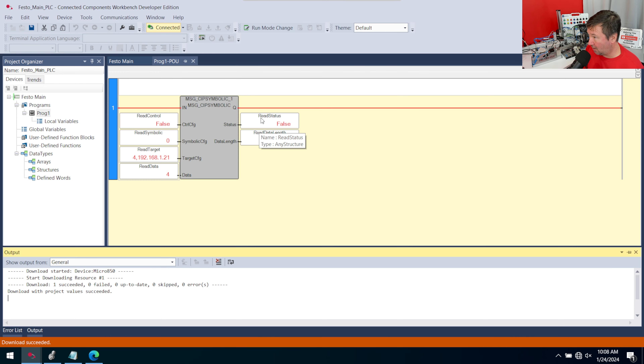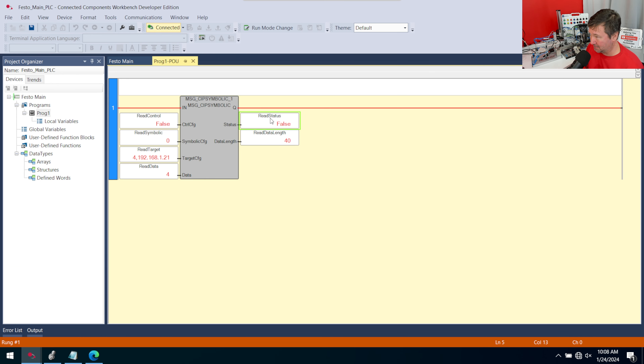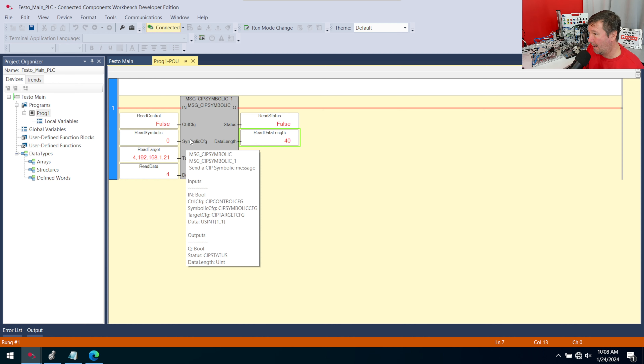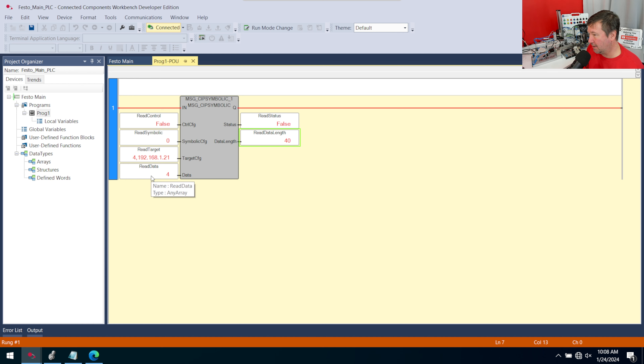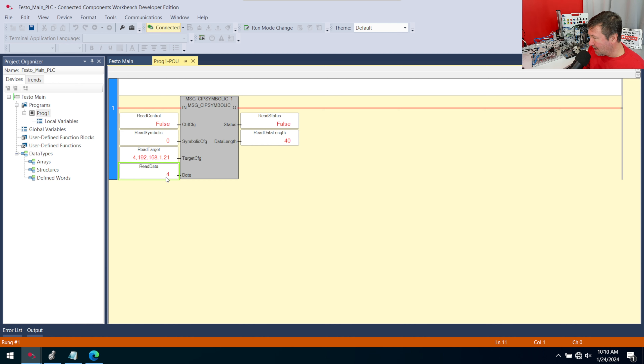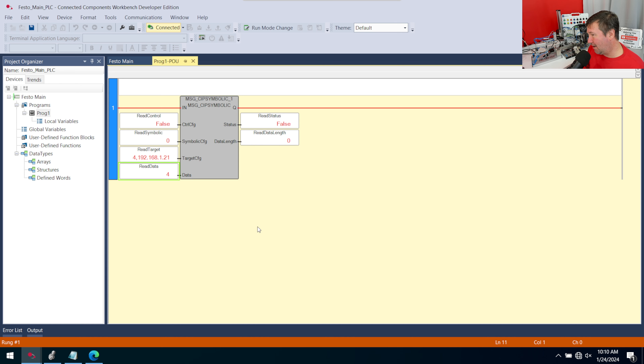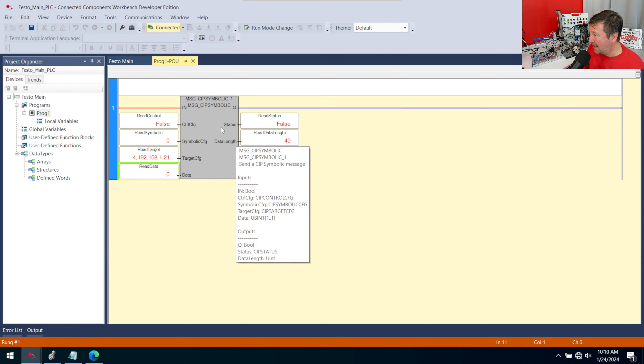You'll notice the data values are bouncing — going from four to zero to four to zero. The read data buffer resets each time the instruction executes again, which is every 20 milliseconds. A lot of people try to use this read data directly and can't figure out why data is bouncing. That's why we need to copy this data once the message has been read successfully.